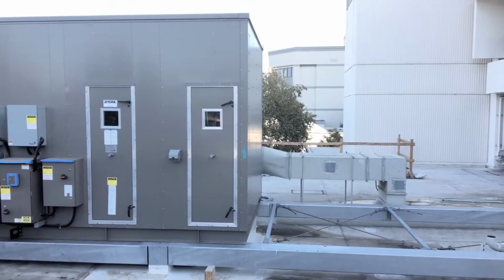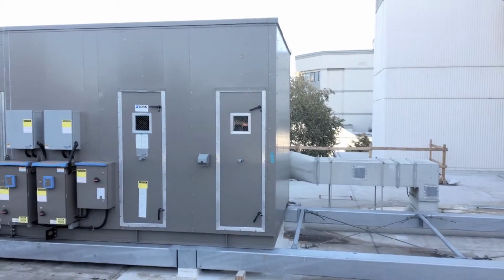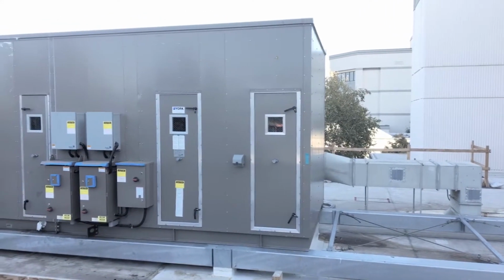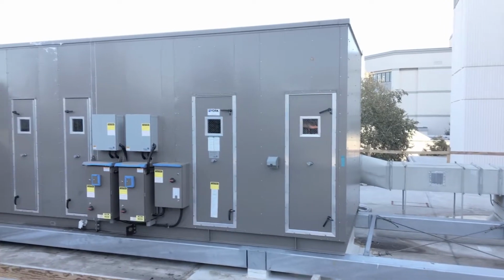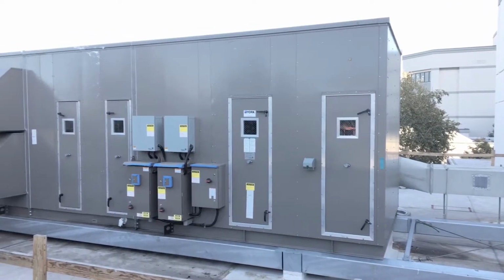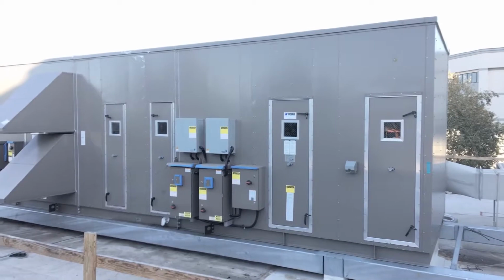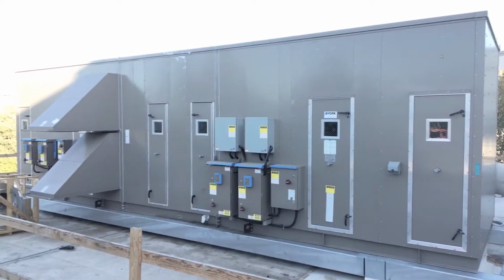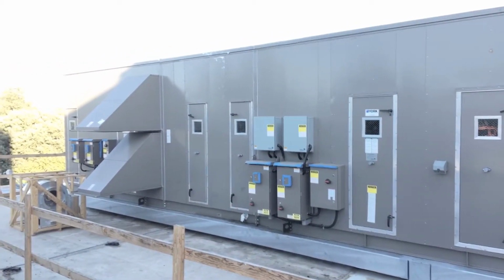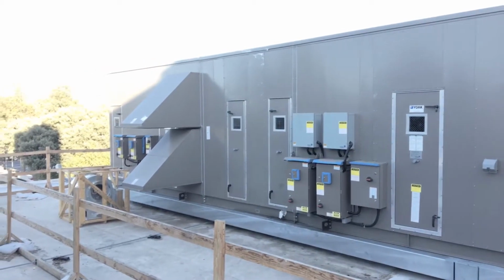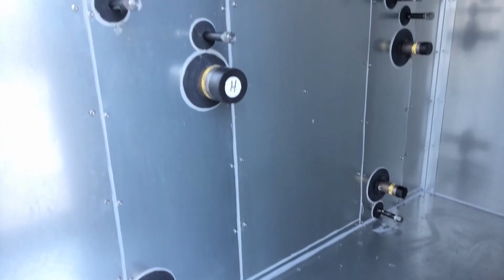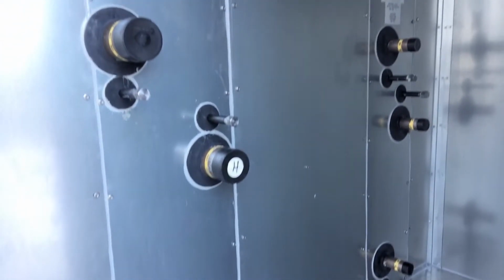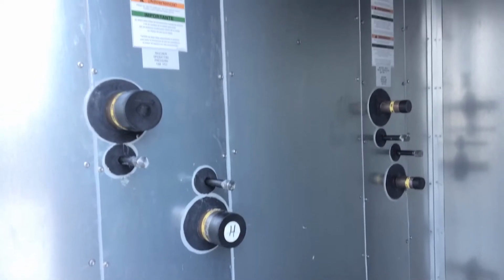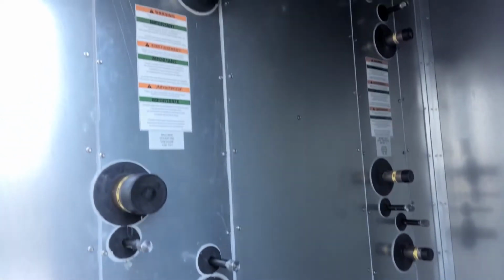There are 2 types of air handler units, draw-through or blow-through. This unit is a draw-through air handler, which means the coils are on the suction side of the fan. An air handler unit, or AHU, usually has an air filter, first set and second set of coils, and a fan. Other items, such as dampers and humidifiers, may be added. The first set of coils gets the heated HTF, and the second set of coils gets the chilled HTF. This is to ensure that on a hot or cold day, the supplied air will remain at the same temperature.